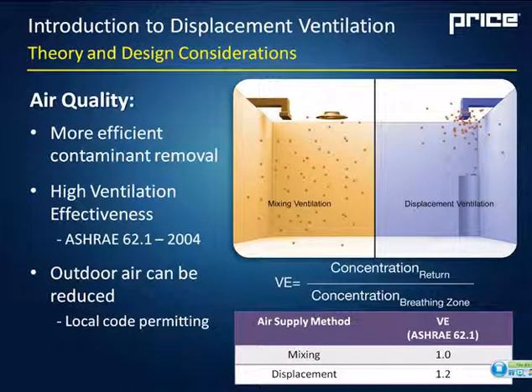I mentioned the air quality can be increased significantly with displacement ventilation. It is a more efficient contaminant removal method simply because we're not diluting the contaminants in the room. We're actually just stratifying, removing them from the breathing zone altogether, and then pulling them out through the returns, which is exactly what we want to do.